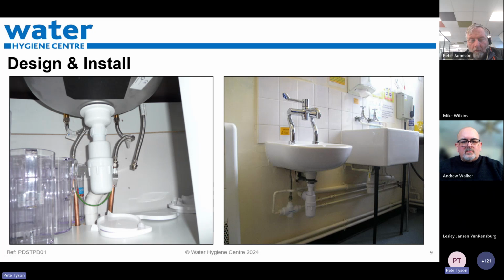These were particularly fitted in an augmented care setting. The contractor's specification of work, the project, the capital team, and the evidence of handover risk assessment identified that these should have been hard plumbed in, with copper pipework and tails fitted to the taps. The reason these were installed is because it's easy and quick, but it's not the right thing to do in augmented care facilities, or in general, because of the potential for that rubber interior to be contaminated - even if they are WRAS approved, the recommendation should be that they are hard plumbed in as best possible.